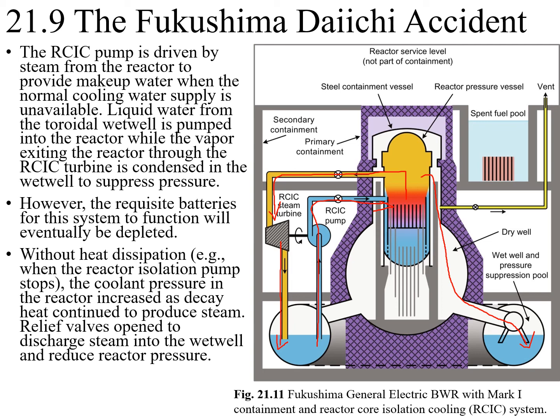Liquid water from the torus wet well is pumped into the reactor, while the vapor exiting the reactor through the RCIC turbine is condensed in the wet well to suppress pressure. However, the batteries required for this system to function will eventually be depleted. In addition, this closed system has no capability of dissipating its heat beyond ambient heat loss mechanisms. Without heat dissipation, the coolant pressure in the reactor increased as decay heat continued to produce steam. Relief valves opened to discharge steam into the wet well and reduce reactor pressure.